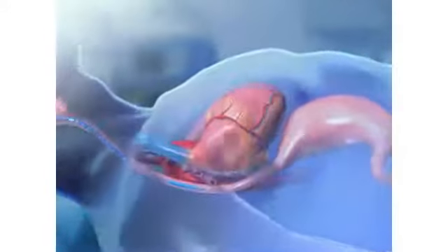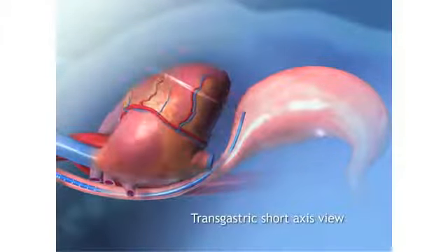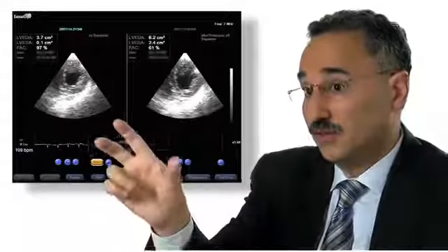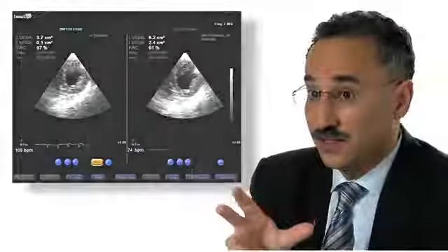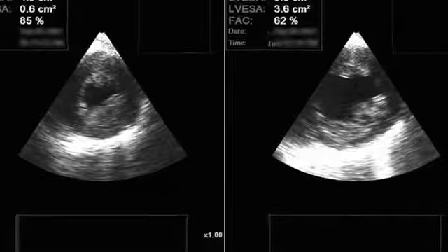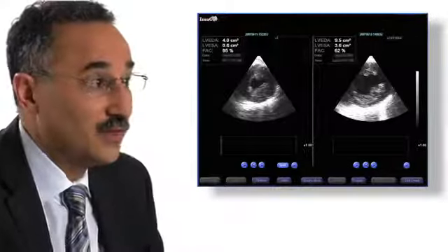Having the capability to leave a TE probe indwelling for up to a period of 72 hours opens up new ways of managing patients' hemodynamics. One of the features of the hTEE system from ImaCor is you can bring up on the screen a split view and look directly at what the patient's heart size and function looked like an hour before, when you were changing some intervention like fluids or pressors, and then compare that directly with what you're seeing right now. That's very powerful to be able to wean off pressors faster. It gives a great deal of confidence.